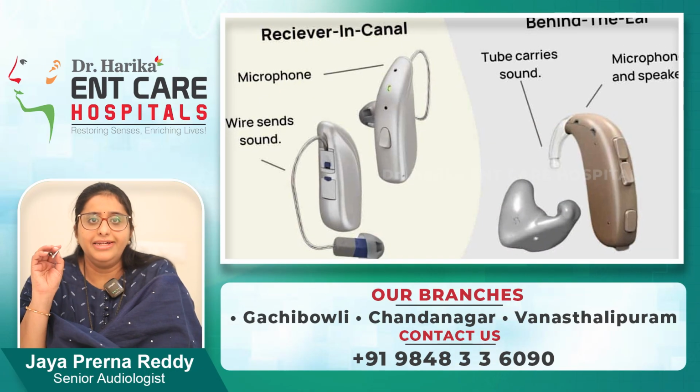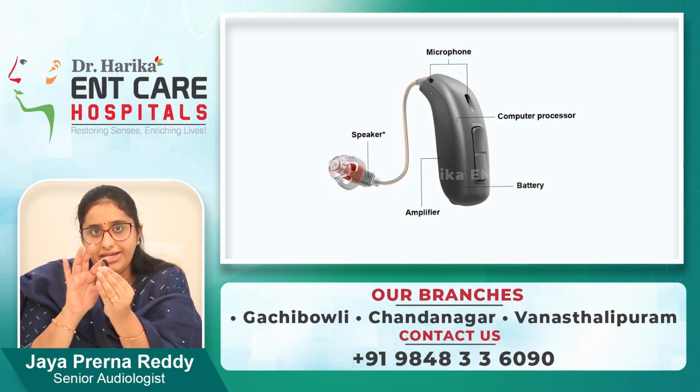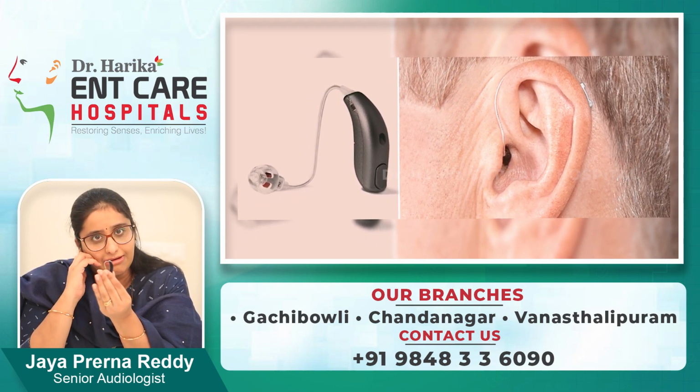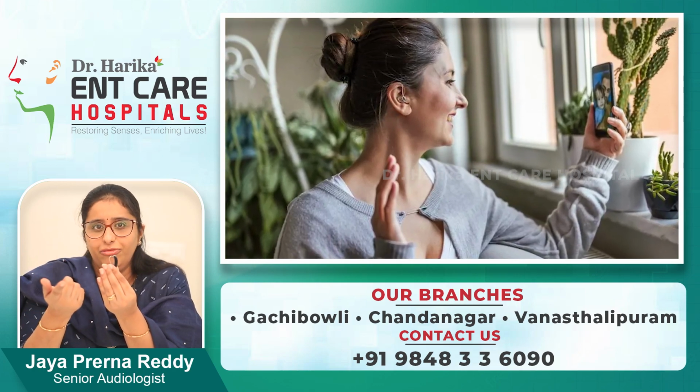The second style, which are commonly seen hearing aids, are RIC and BTE. Now, what is RIC? RIC is receiver in the canal. I told you there are three parts in a hearing aid. The microphone and amplifier are in the casing, but the receiver of this hearing aid goes inside the ear. Whatever sound is heard is much clearer and much more natural for the patient to listen to.